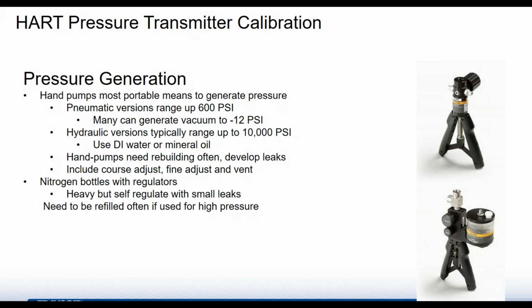For higher end pressure, you may need to go to a hydraulic pump, and that's the one you see on the bottom right. That would use something like mineral oil or distilled water, and that will get you up to about 10,000 psi. Lastly, some of the guys out there will carry a nitrogen bottle with a regulator. So that's challenging. You've got a heavy bottle you carry around. It's got a regulator on it so you can mitigate small leaks. But if you're using it for high pressure, sometimes you're going to have to replace it with another bottle or refill it, that sort of thing. So those are the pressure sources that the techs are going to be using out in the field.